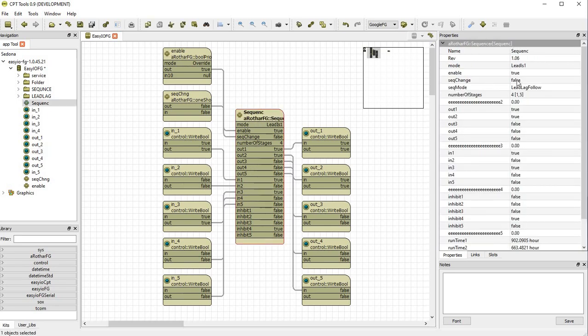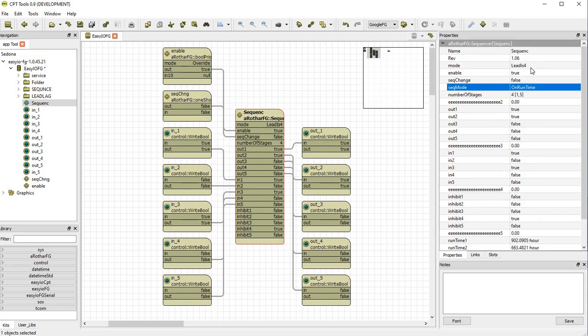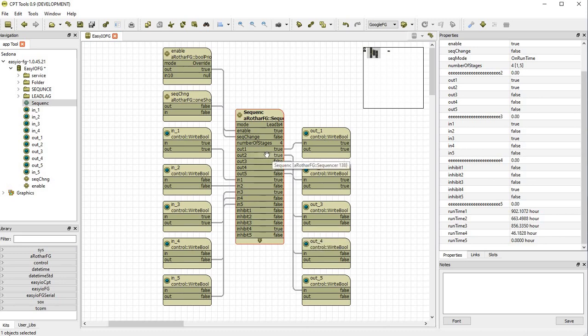If we change this to runtime, the lead is selected as four because four will have the least amount of runtime. So four is currently in fault. So the next one will take the lead, the least amount of run hours which in this case is two. So two will be leading and then three and then four.